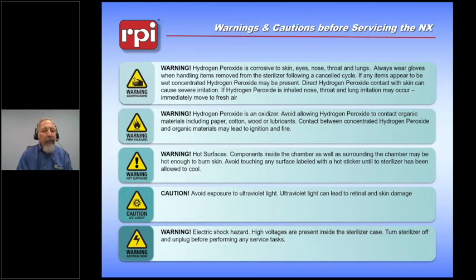So in talking about hydrogen peroxide sterilizers, this does apply specifically to hydrogen peroxide sterilizers. This is a list of warnings that everyone who touches this machine or has work under the cabinet should be aware of. One in particular that I might point out is that when you open the door of the peroxide sterilizer at the end of the run, there is still a possibility there might be some small amount of hydrogen peroxide left within the chamber. You just don't want to put your nose directly in front of the door when you open it. Just make sure that you let the air within the chamber dissipate a little bit before you pull the material out. Thank you.